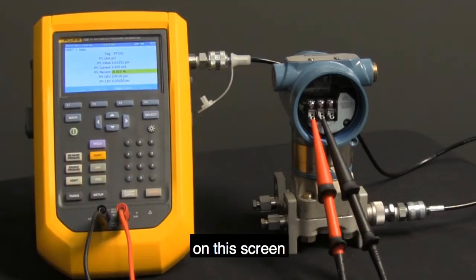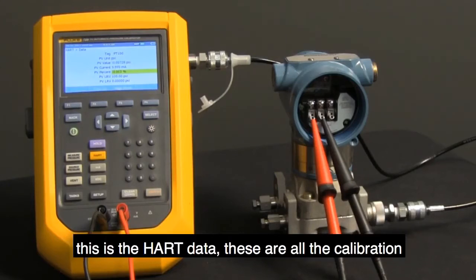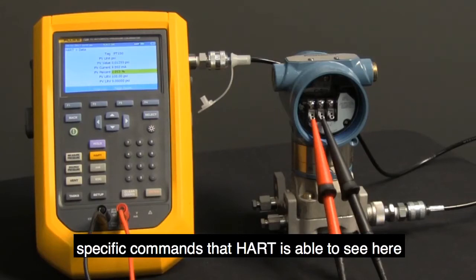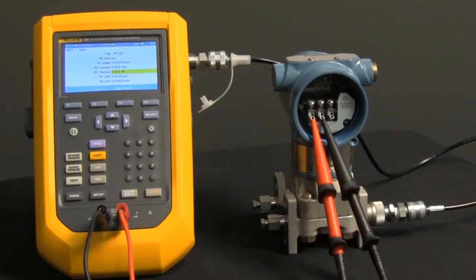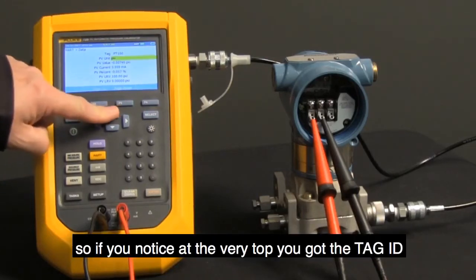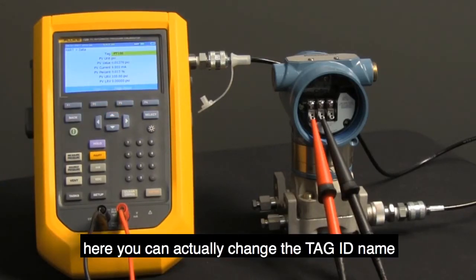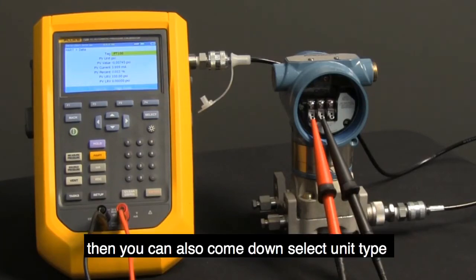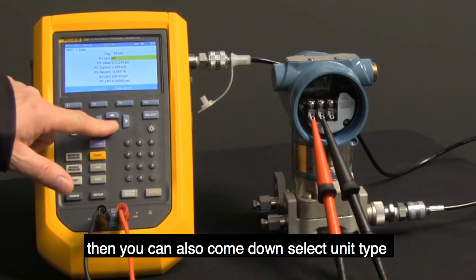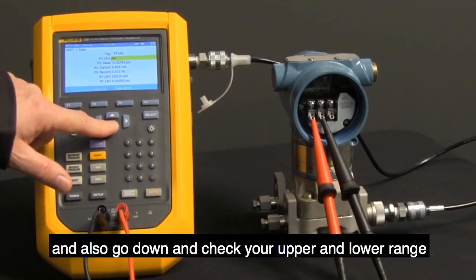On this screen, this is the HART data. These are all the calibration specific commands that HART is able to see here. At the very top, you've got the tag ID, and here you can actually change the tag ID name. Then you can also come down, select unit type, and check your upper and lower range.